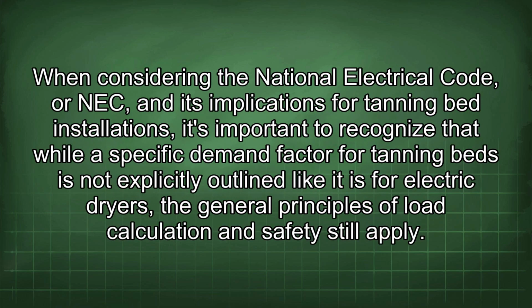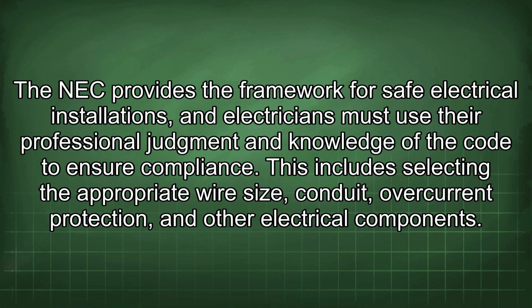When considering the National Electrical Code, or NEC, and its implications for tanning bed installations, it's important to recognize that while a specific demand factor for tanning beds is not explicitly outlined like it is for electric dryers, the general principles of load calculation and safety still apply. The NEC provides the framework for safe electrical installations, and electricians must use their professional judgment and knowledge of the code to ensure compliance. This includes selecting the appropriate wire size, conduit, overcurrent protection, and other electrical components.